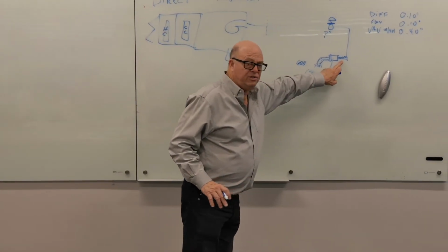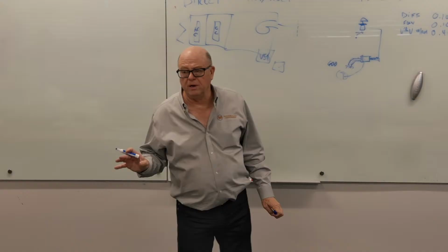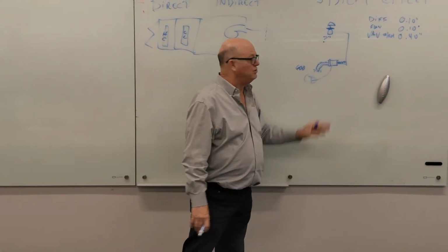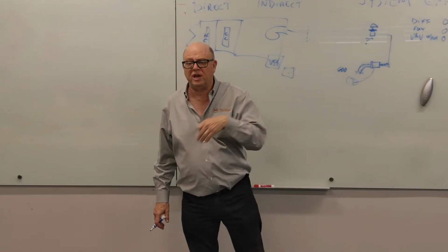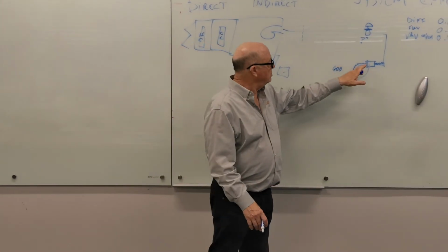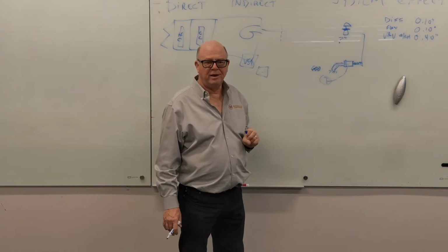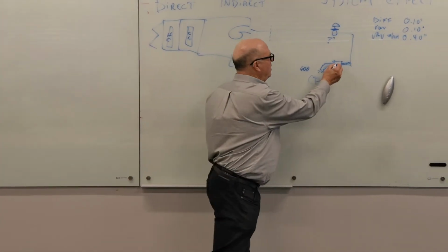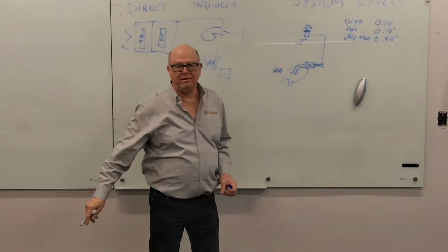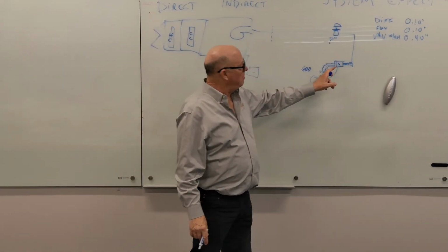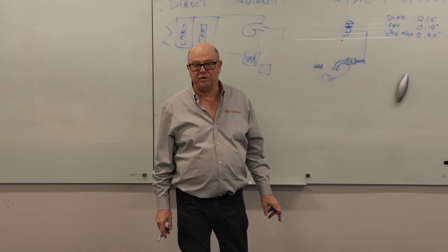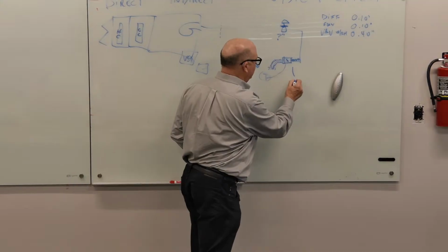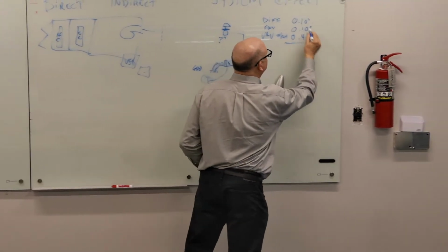Now you've got the high side duct, and when you're talking to the sheet metal foreman, and it's a TI job, and you're putting in VAV boxes, he's going to talk to you about high side and low side. Well, the low side, why do they call it low side? Because it's lower pressure. So you've got a damper in there, right? You're having to give this box a certain amount of pressure to get the air out. How much pressure do you have to have right at this point?